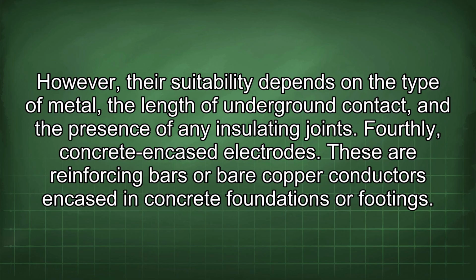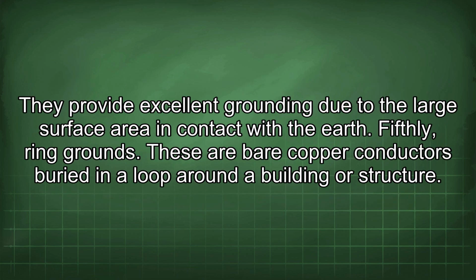However, their suitability depends on the type of metal, the length of underground contact, and the presence of any insulating joints. Fourthly, concrete encased electrodes. These are reinforcing bars or bare copper conductors encased in concrete foundations or footings. They provide excellent grounding due to the large surface area in contact with the earth.